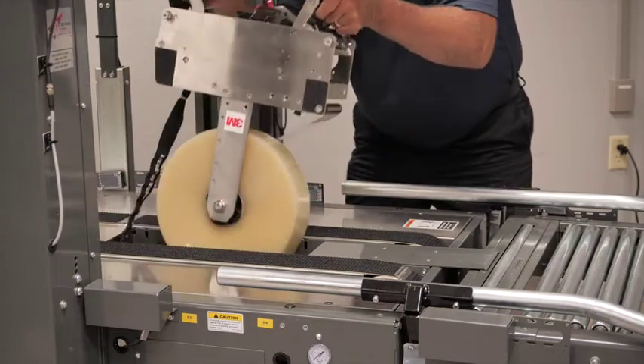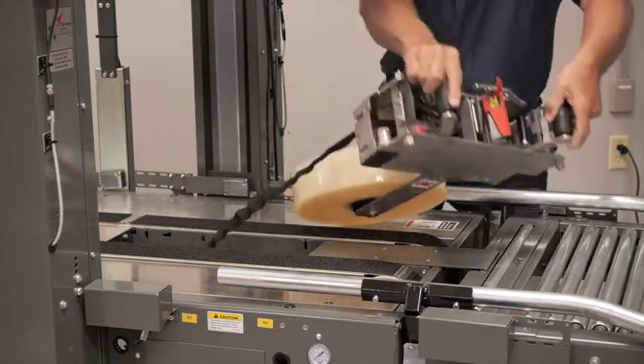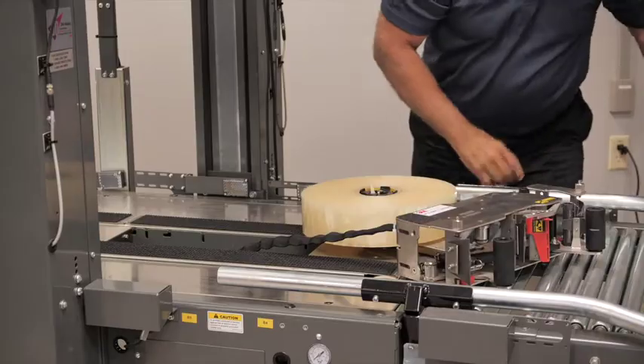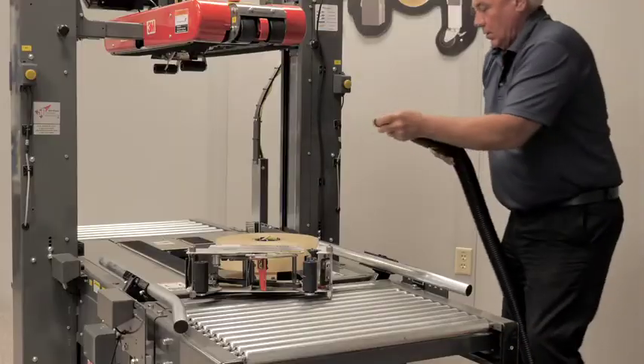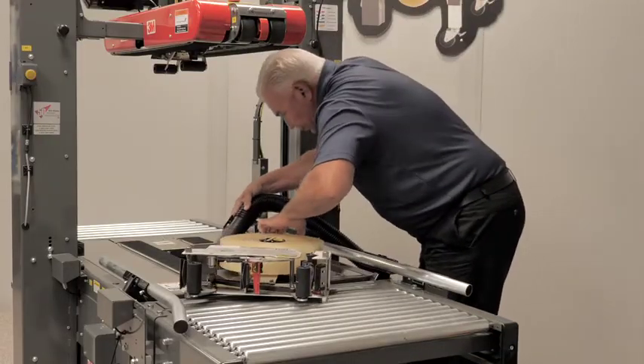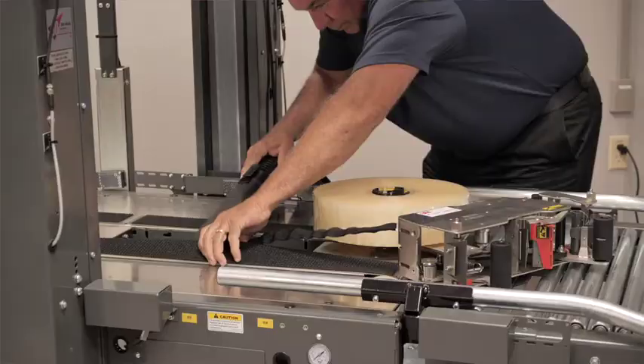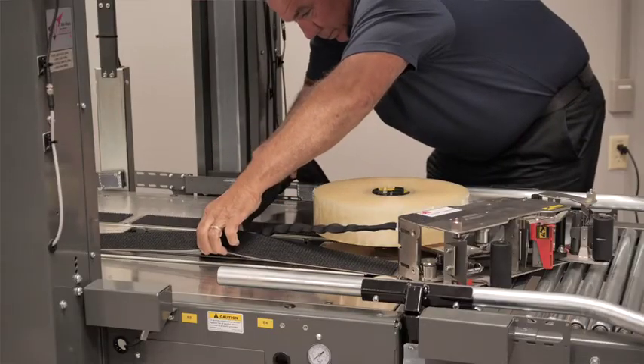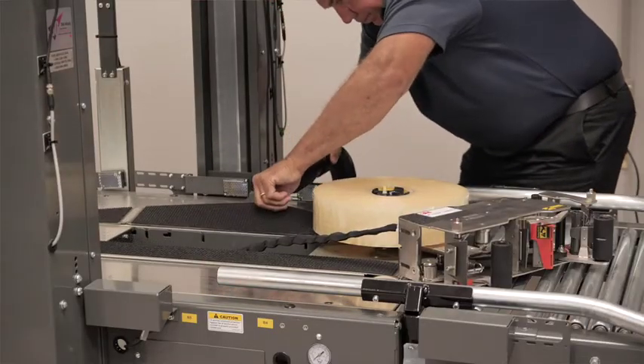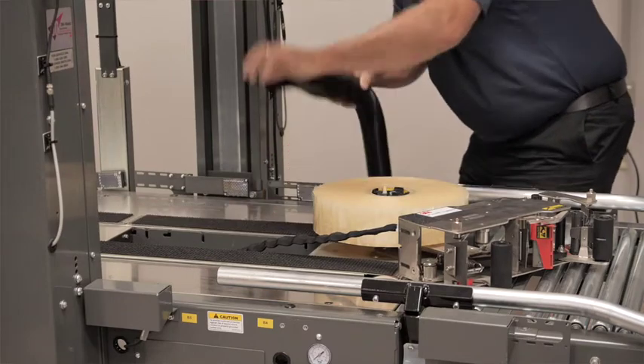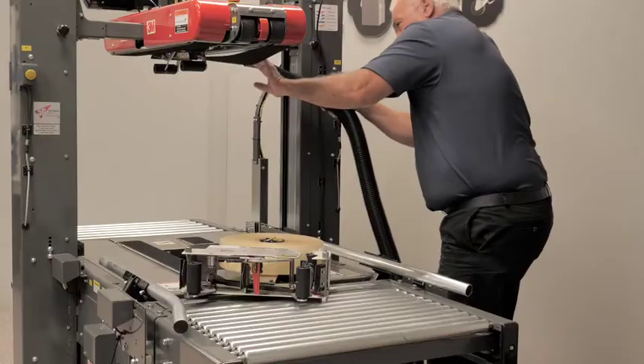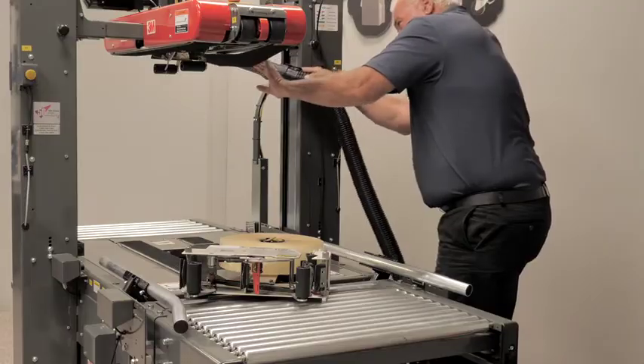A vacuum cleaner can assist during this operation, but never use compressed air to blow the dust as this can be hazardous. Remove the lower taping head and clean it along with the cavity using the rag and vacuum as necessary. Repeat this procedure on the upper assembly, noting that it can be easier to lower it first by repowering the machine. If so, be sure to remove power from the machine before cleaning the upper assembly.